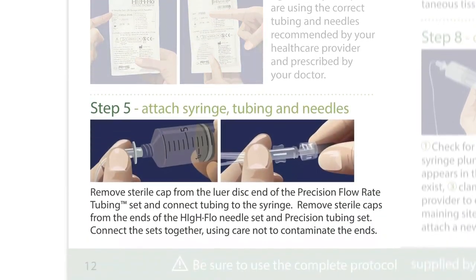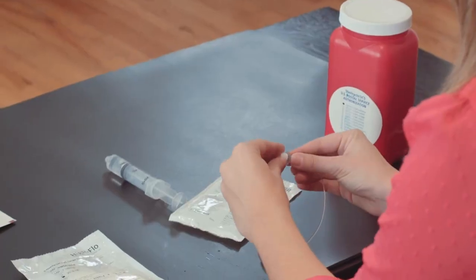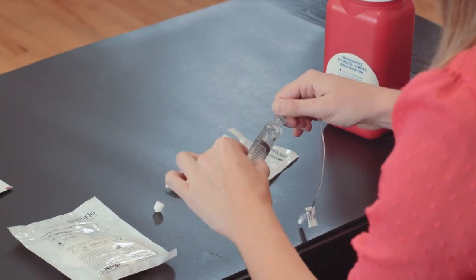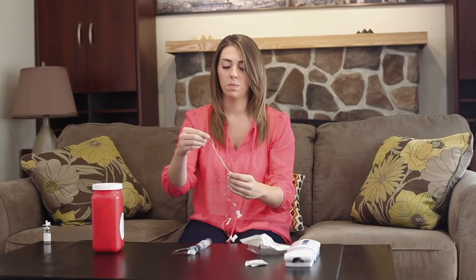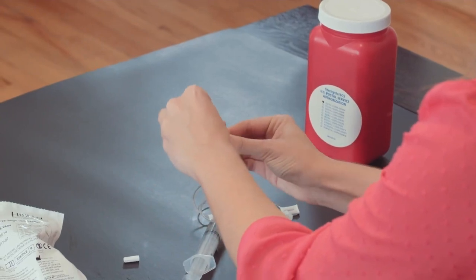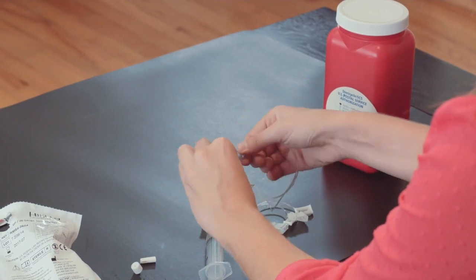Step 5: Attach syringe, tubing, and needles. Remove the sterile cap from the luer disc end of the Precision Flow Rate tubing set and connect the tubing to the syringe. Remove the sterile caps from the ends of the High Flow Needle Set and Precision Tubing Set. Connect the sets together, using care not to contaminate the ends.